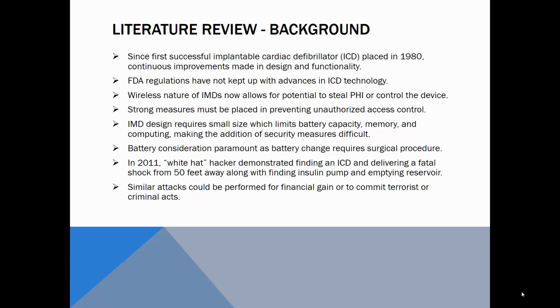One of the main issues seen in the literature is that the inherent nature of IMD design requires a small size. This significantly limits battery capacity, memory, and computing, which makes the addition of security measures quite difficult. Specifically, the battery consideration is a paramount concern, as battery changes require a surgical procedure to remove the device, replace the battery, and then reimplant it.